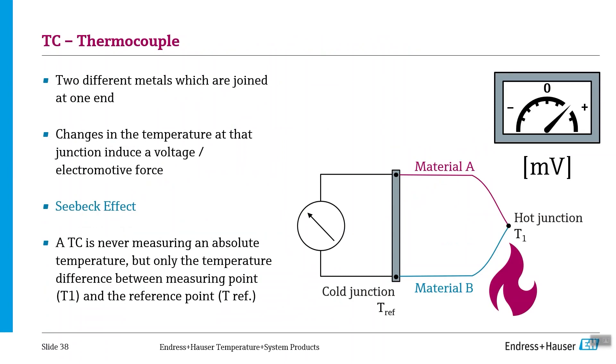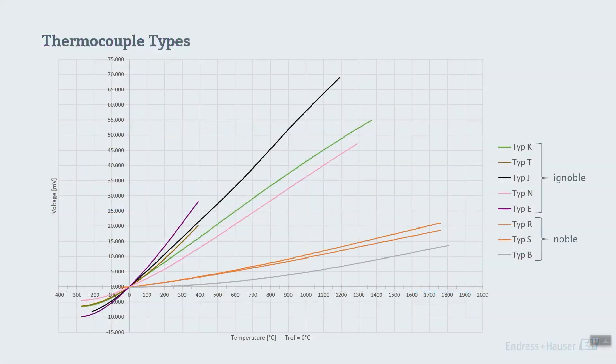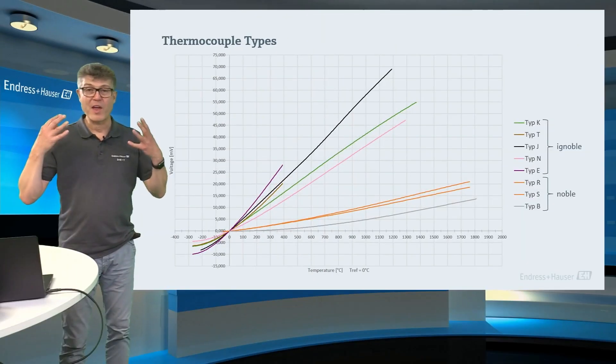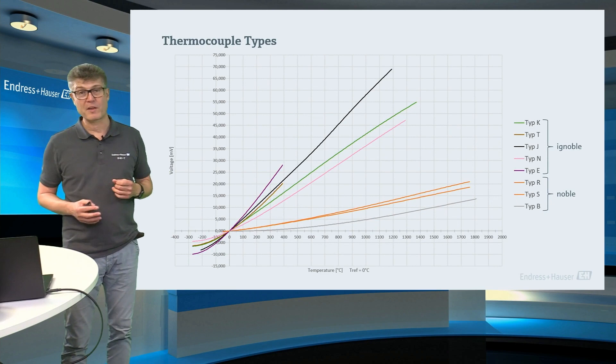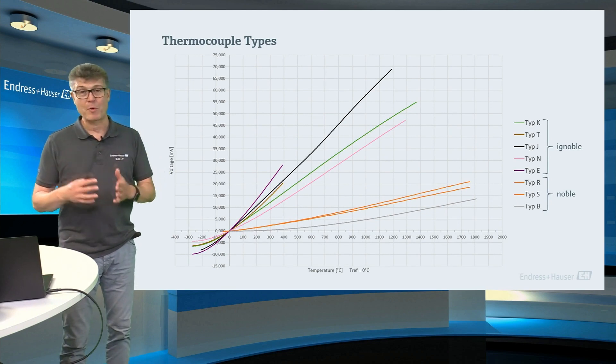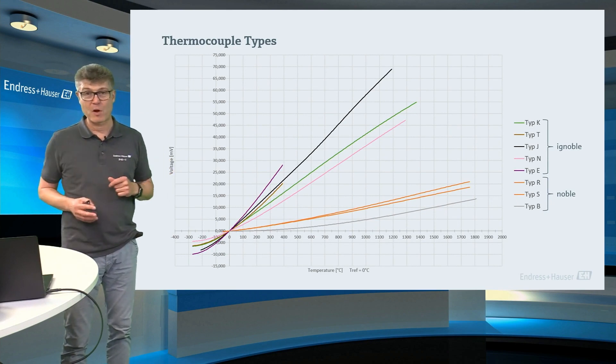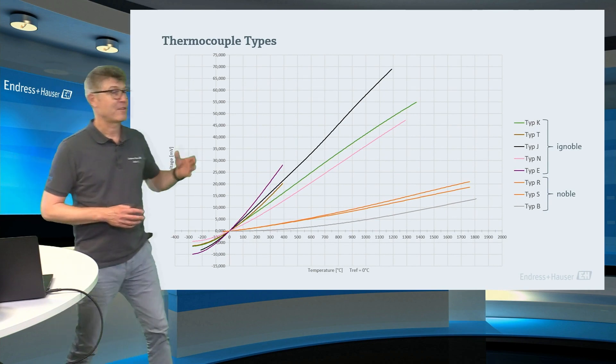The thermocouple voltage is quite small. Microvolts or millivolts. And this needs quite accurate electronic in the temperature transmitter. There are several already standardized thermocouple pairs. So, two different alloys or metals. Let's focus on a few.